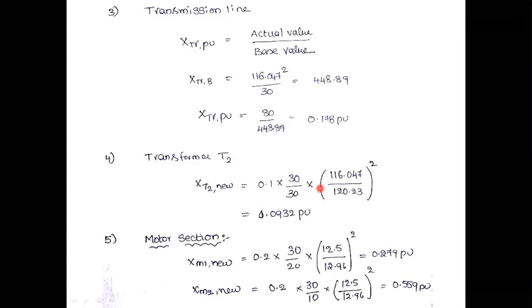Once again, I'm going to remind you that whenever you substitute the value of the voltage source in per unit, that means E_G1, E_G2 or E_M1, E_M2, whatever it may be, you need to consider the formula actual voltage by base voltage, where the base voltage is the one we have to consider for that entire section. As far as this particular problem is concerned, E_G1 is 13.8 by 13.8, which is equal to 1 per unit. Similarly, E_M1 is equal to 12.5 by 12.96, which is 0.965 per unit. Similarly, E_M2, so E_M1 and E_M2 are equal.